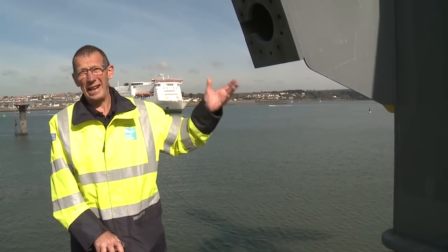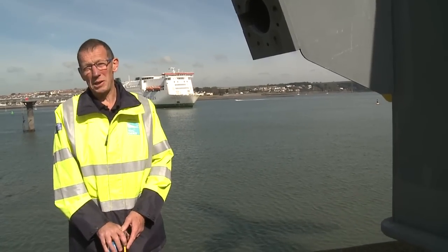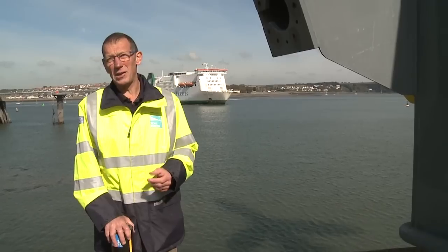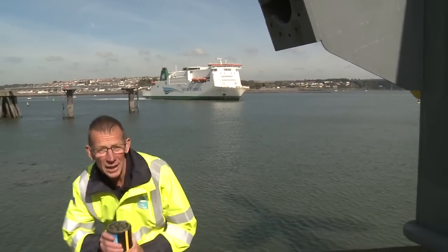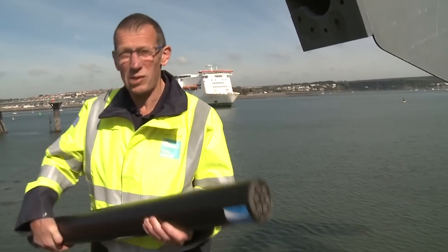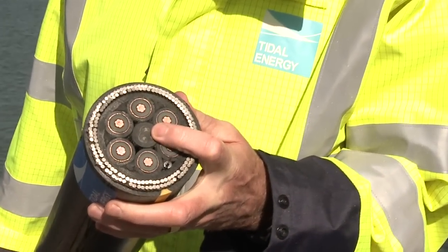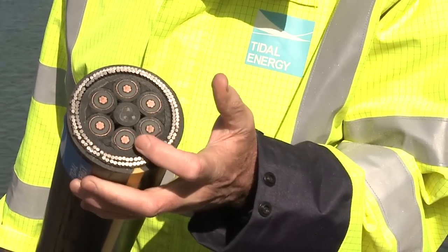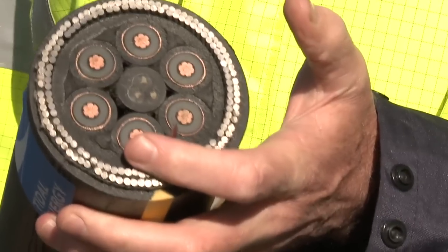Connecting a turbine like this electrically is no easy matter. We've already laid our submarine cable into Ramsey Sound — 1,400 metres of it. When we install the device, the first task is to recover the end of that cable. The cable shown here is a sample: just one metre weighs 17 kilos. It contains six power cores — three used to import power to the device and three for exporting power — along with 24 fibre optic lines used for control and data acquisition.